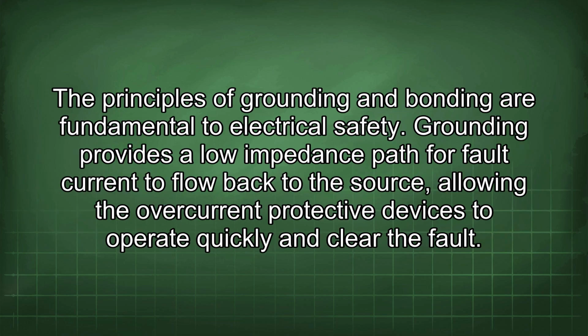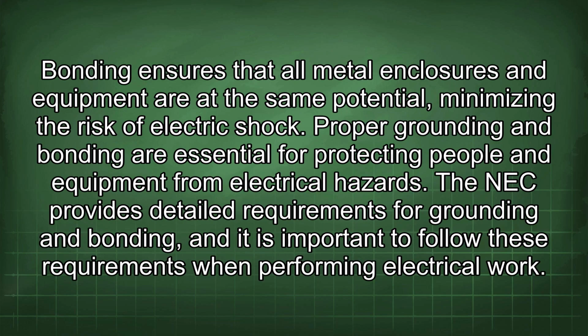The principles of grounding and bonding are fundamental to electrical safety. Grounding provides a low impedance path for fault current to flow back to the source, allowing the overcurrent protective devices to operate quickly and clear the fault. Bonding ensures that all metal enclosures and equipment are at the same potential, minimizing the risk of electric shock. Proper grounding and bonding are essential for protecting people and equipment from electrical hazards.